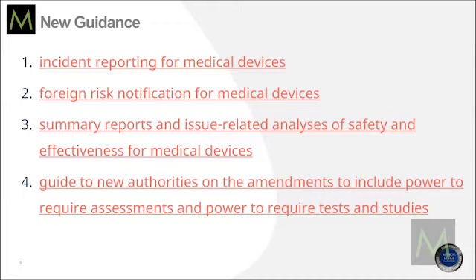If you're not CE marked and you're one of those companies that has FDA and Canada or just Canada, you suddenly have a lot more work to prepare for. They've split it up very similar to Europe: for high-risk devices you have to do these annually; for low-risk devices like a Class I product, only every other year — biannually. Depending on your risk classification, you'll have different timelines for how frequently you generate these reports. If you're a Class I only company working with distributors who have a license, they have to produce these reports.